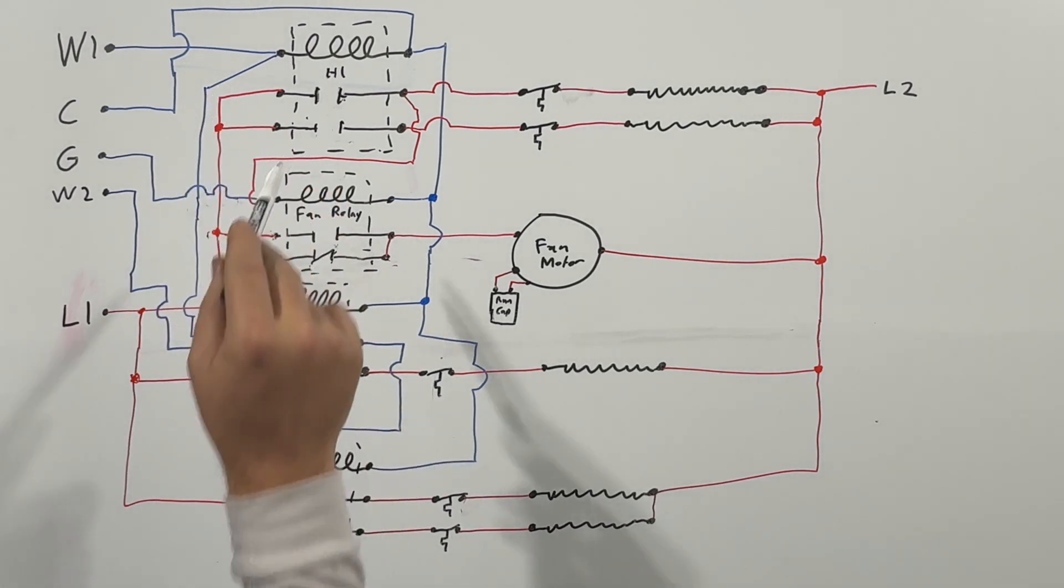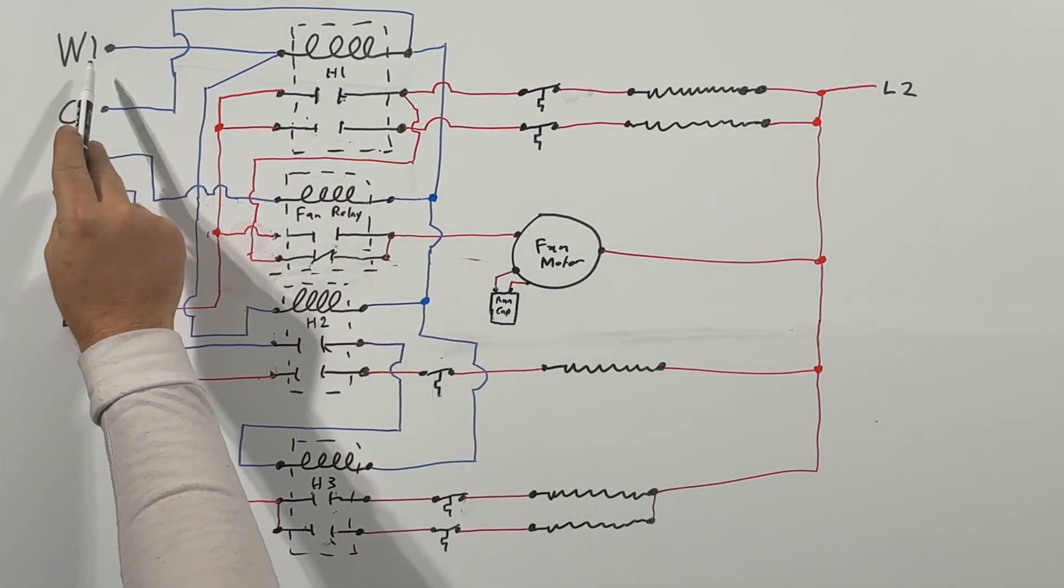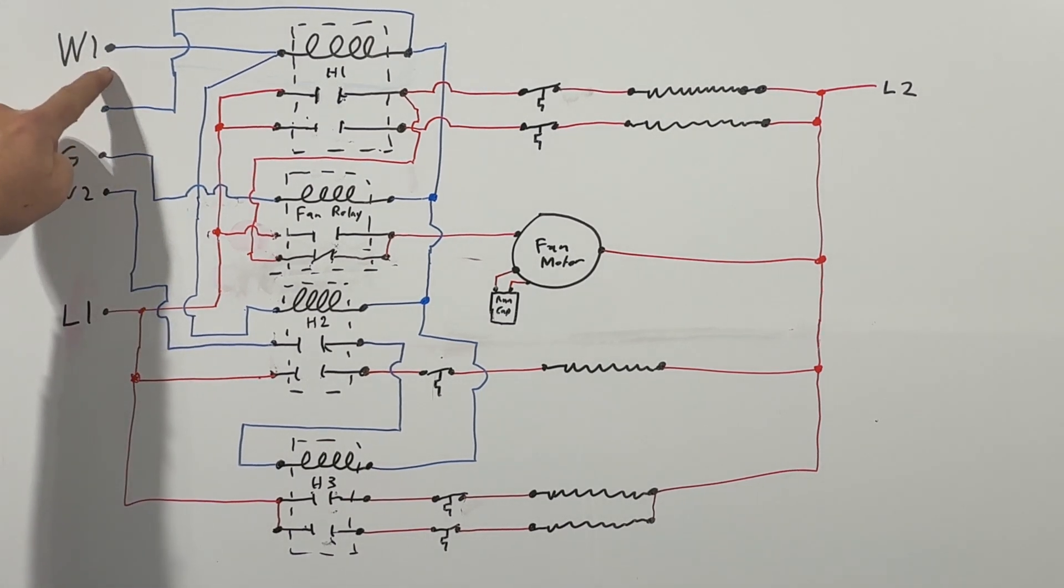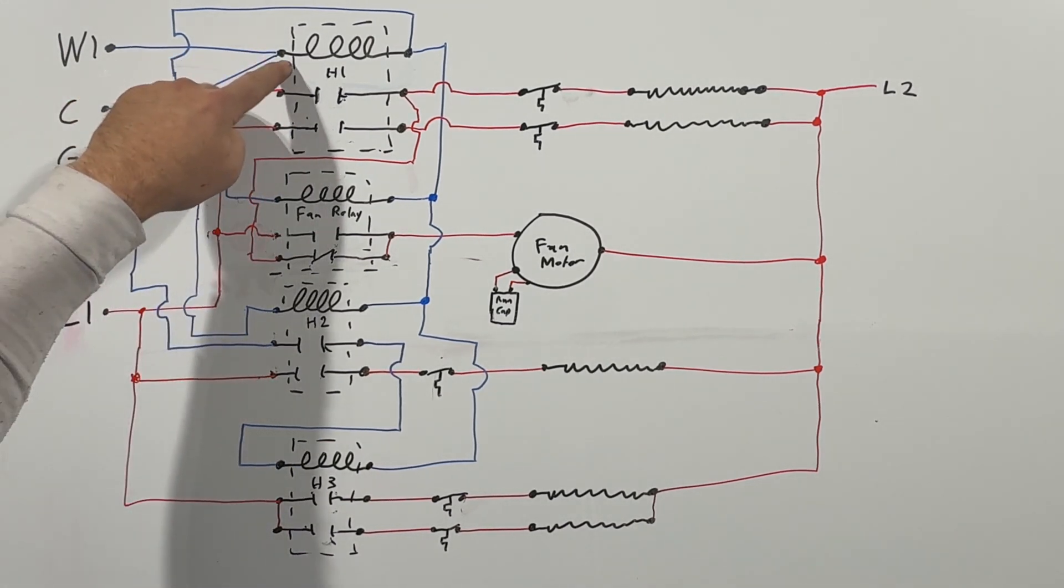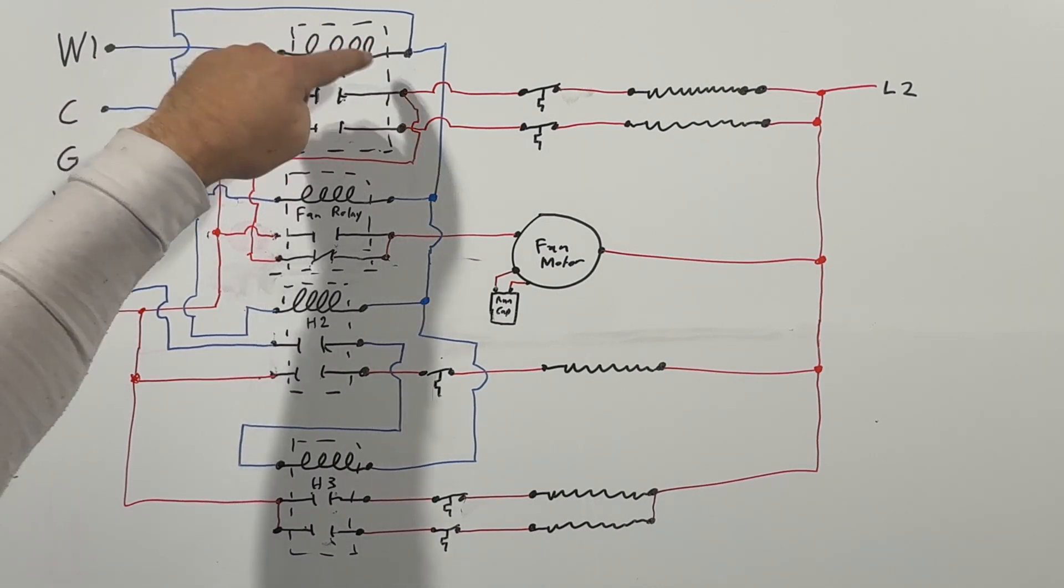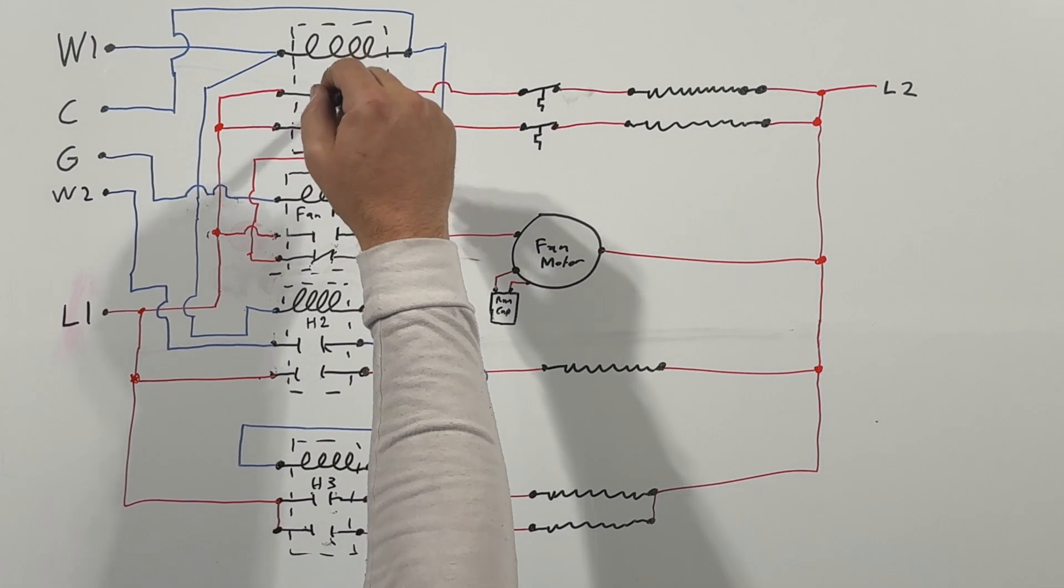Anyway, so if we're calling for heat, we're going to energize 24 volts to W1, right? So we're going to have W1 having 24 volts, which is going to travel into our heating element or our coil in this case, and it's going to warm that thing up.